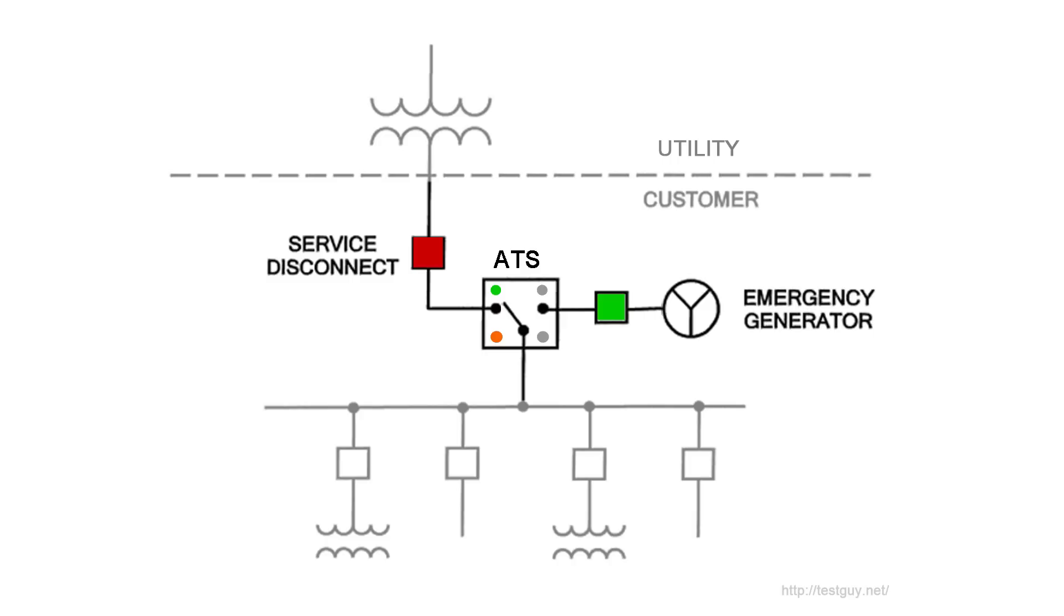Step 2. Close the alternate source breaker and start the engine generator. The alternate source available lamp will illuminate when correct voltage and frequency levels are sensed. After both sources have been verified, shut down the engine generator and put the generator's start control in the automatic position.